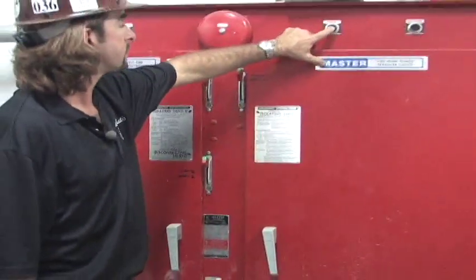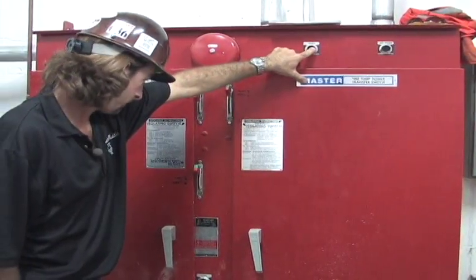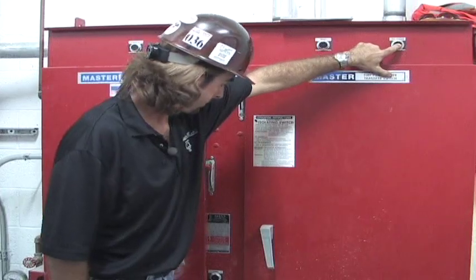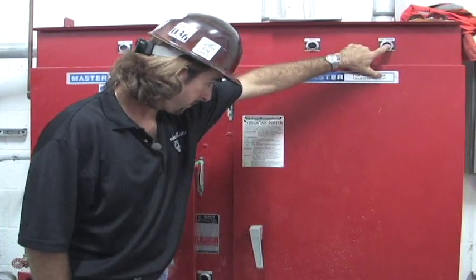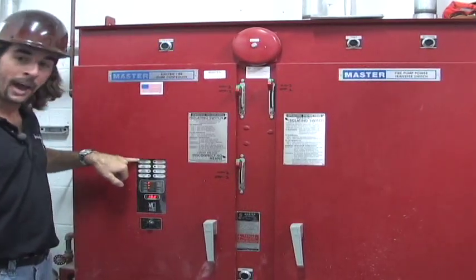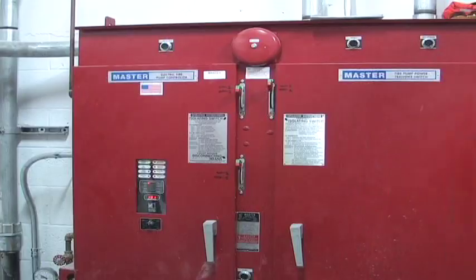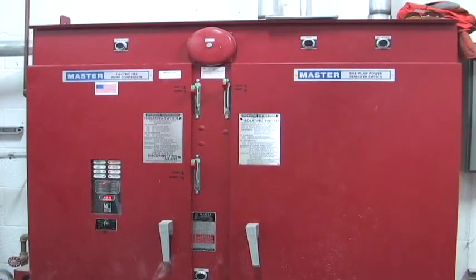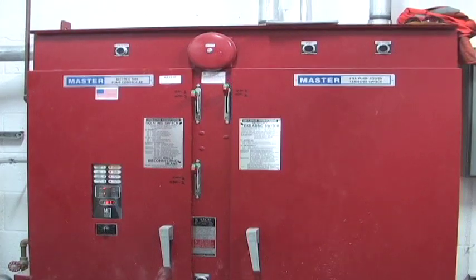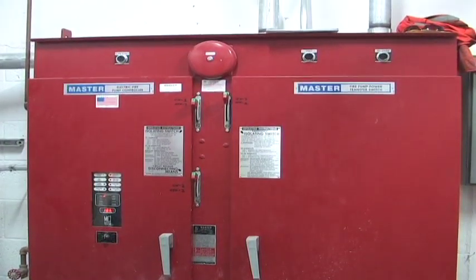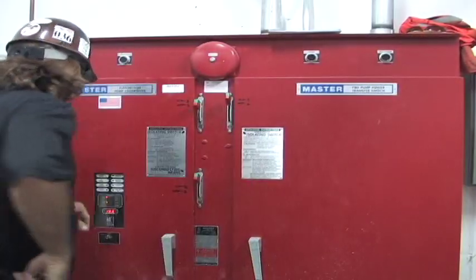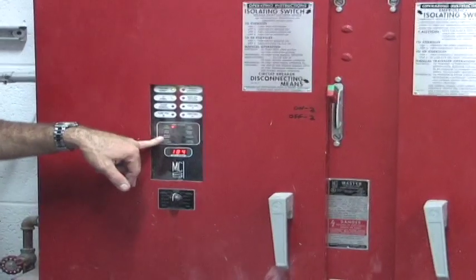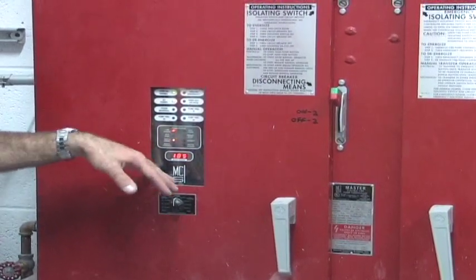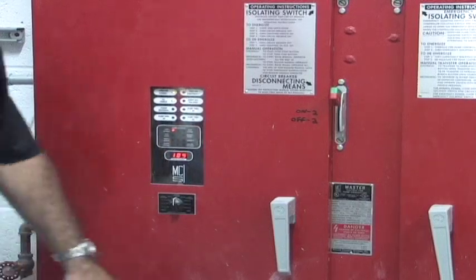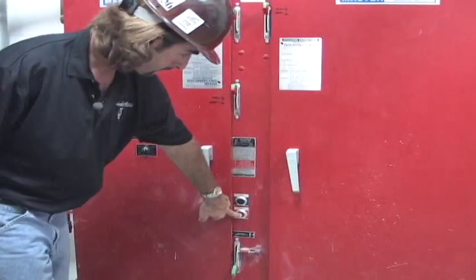We're going to transfer this back to normal power. Excuse me, wrong button. We came back, now we're back to normal power. We have our timer run light right now, which, like I said, is going to run for 10 minutes, and then it'll automatically shut the fire pump off. Little timer right there.